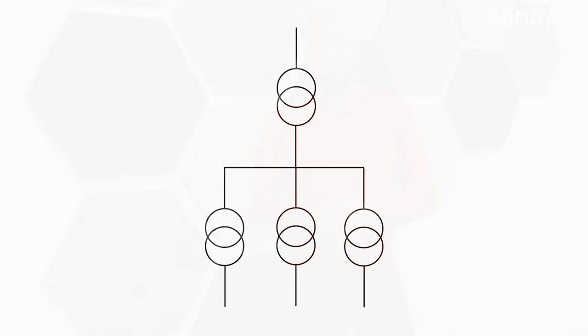With this basic understanding we now have a model we can apply to a larger grid to understand how harmonics are spreading — moving from one facility to another or from one load to another, which in our model is the same thing. Consider a picture of a larger grid with several loads and several transformers identical to the previous example: a large feeding transformer supplying this part of the grid, and smaller transformers going down to variable frequency drives, all producing harmonic current.